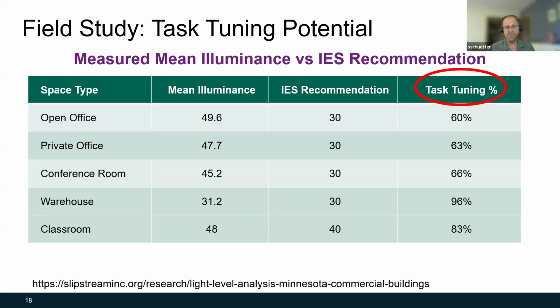Summarized here in this table are the mean measured illuminances we found, the IES recommended illuminances, and the task tuning percentage, which is the maximum lighting power limit in a task tuning scenario. Note that implementing the task tuning percentage would bring the actual and recommended light levels into alignment. You'll note that for all space types, the mean measured illuminance was higher than the IES recommendation, indicating in several instances significant opportunity to both capture energy savings and improve lighting quality by minimizing the potential for glare from overlit spaces.